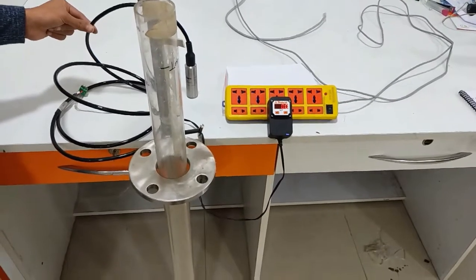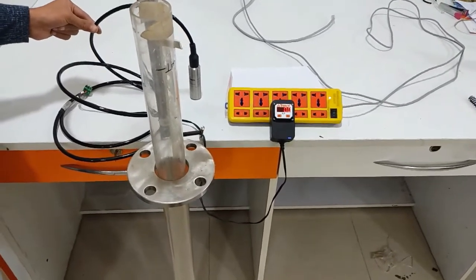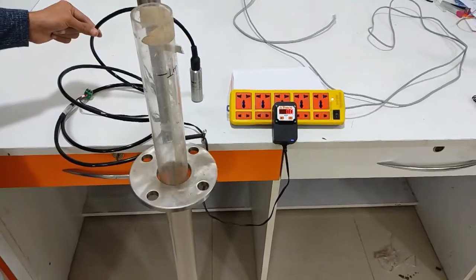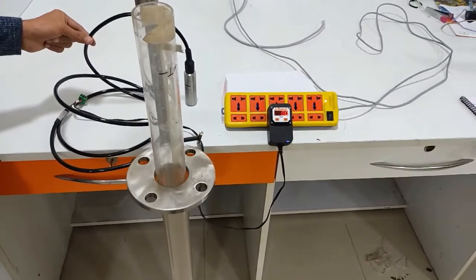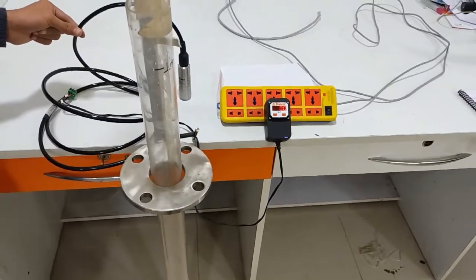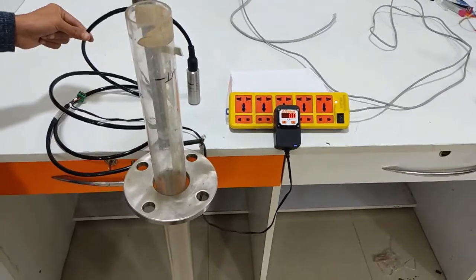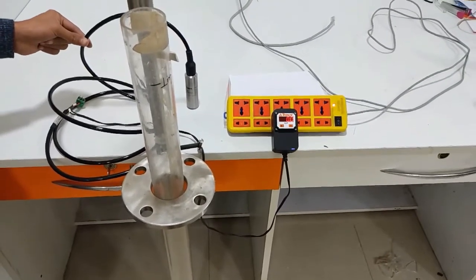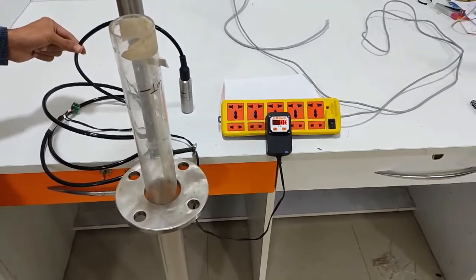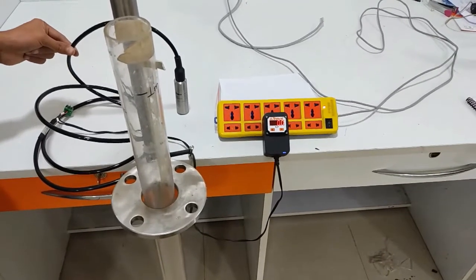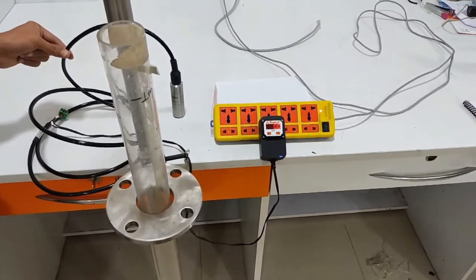We are using a 0 to 1 meter hydrostatic level transmitter with 4 to 20 mA output. We are using a display which is loop powered with 4 to 20 mA output. The display is set from 0 to 100%, where 0% means 4 mA and 100% is 20 mA.